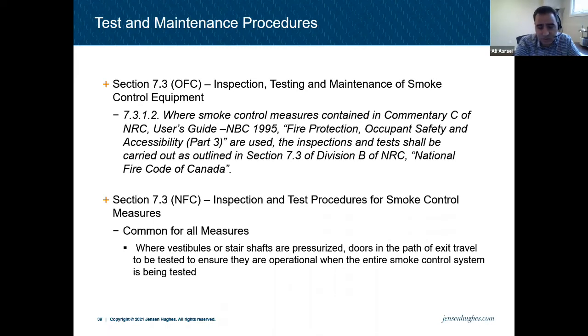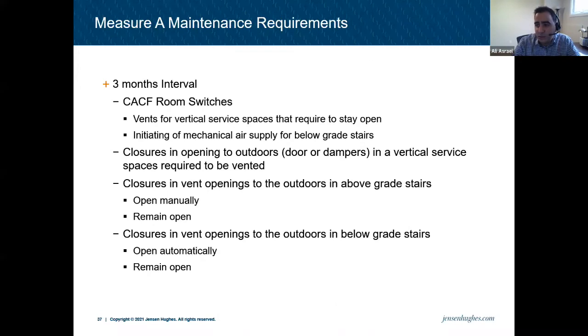So this is one of the tests that we do. We put the entire system, not only one shaft or one vestibule here and there, it has to be the entire system because they affect each other. When you have them all running, it's different than when you have one of them running. Let's say I'm testing the doors for this pressurized stair. If I turn only that on, I may get different numbers than when I turn on the entire system, right? So we have to make sure that the entire system is working and then do the measurement. And there were other tests at 3 month intervals.